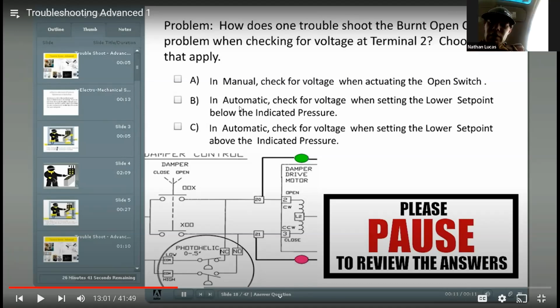It's burnt out right there, between 2 and L2. But you've got your probe on terminal 2, so do you expect to see a voltage? Yes. What do you expect to see? 120. Okay. In automatic, should we check for voltage when setting the lower set point below the indicated pressure? Would that do anything for us? No. Okay, in automatic, check for voltage when setting the lower set point above the indicated pressure. Yeah. Okay, let's see what they say, Dave.